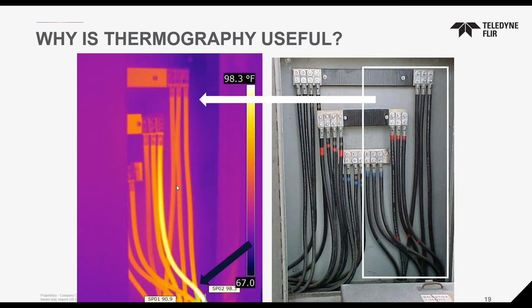There was actually an issue about 100 feet away from this junction box that was causing this overheating. So we're able to see it here, trace it back to its root cause, make that fix, make that correction, and then everything was good to go. Left alone, left unattended, this would have become a major disaster—potentially an electrical fire, overheating at this junction box.